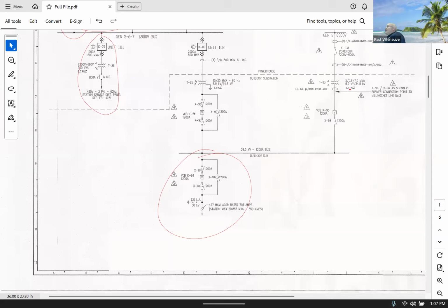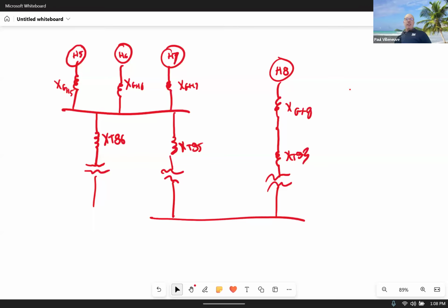So under 35 kV, vacuum breakers work really well for medium voltage conditions like 4160 and above. Below that, you usually just use open air because that's not too big of a deal. But this is using vacuum. But again, it's just a breaker. And then it goes to no man's land, so we're not even going to worry about it. So this was essentially what you needed to create, at least from a base level.